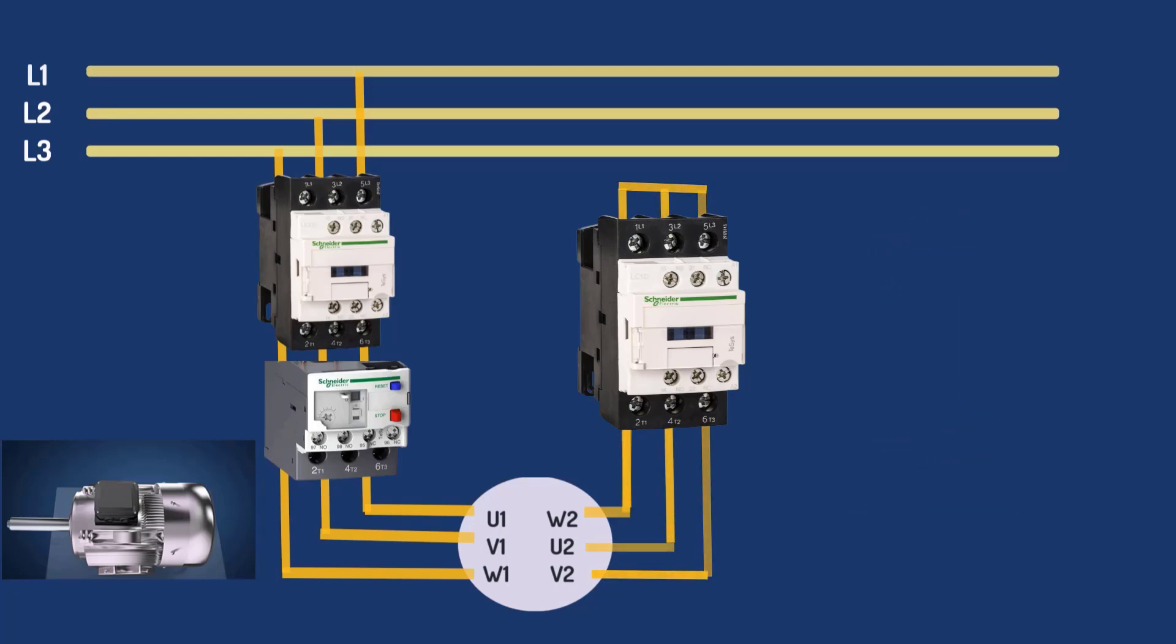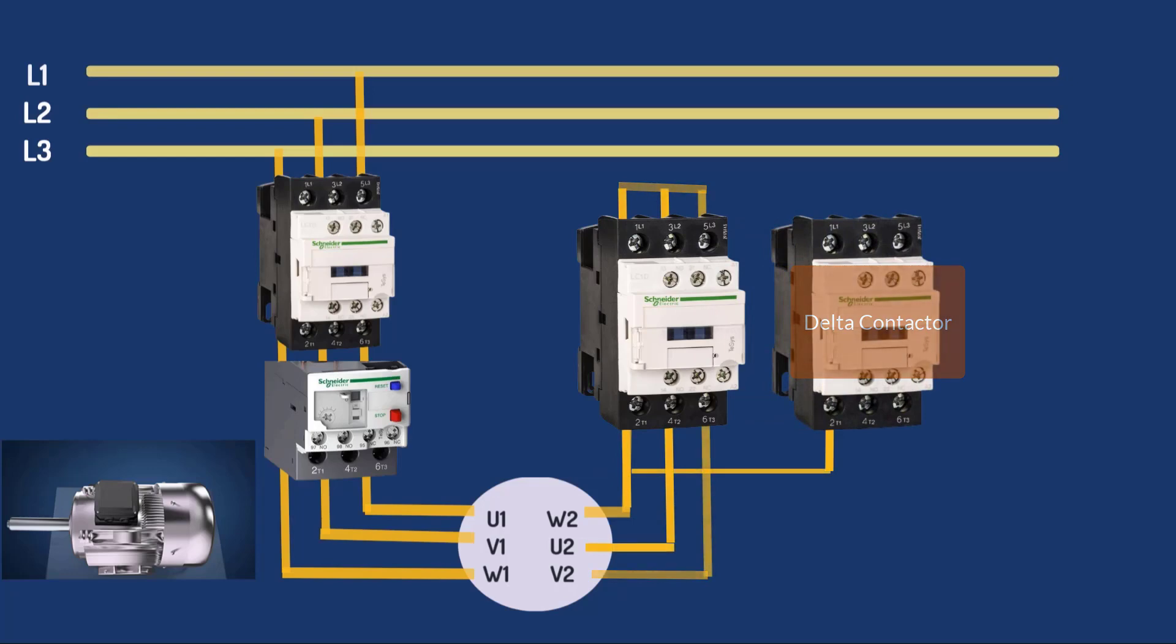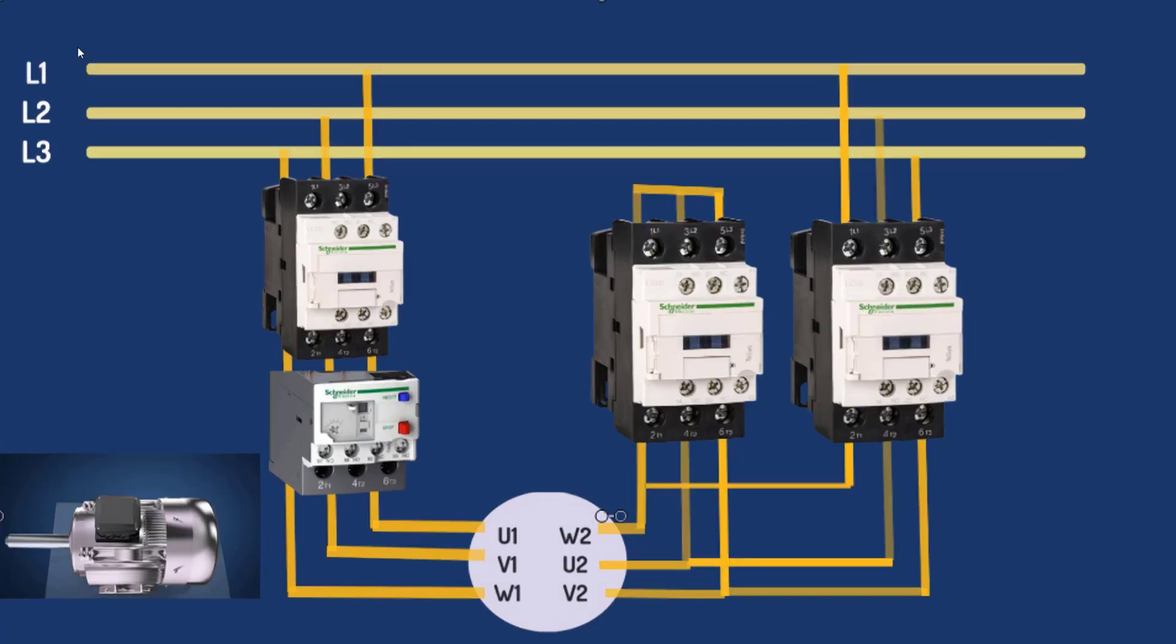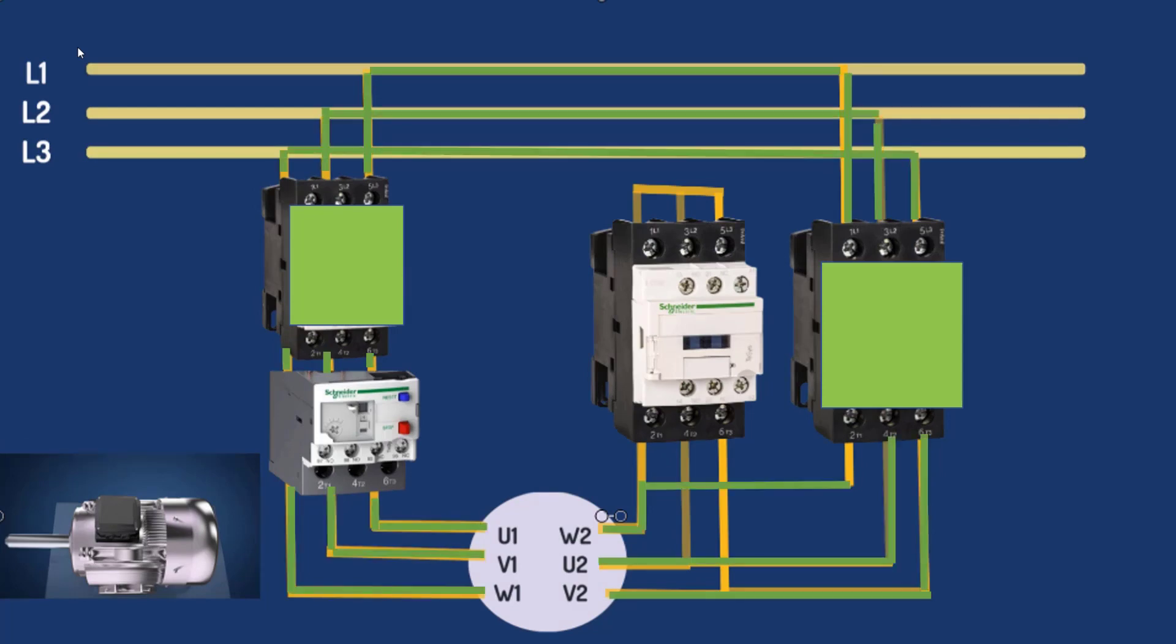Which means the delta contactor is now on. In delta motor winding connection, we will add another contactor here and connect it to W2, U2, and V2 terminals of the motor. We would wire the other end of the contactors to L1, L2, and L3 respectively. When main and delta contactors are energized, U1 will be connected to W2, V1 to U2, and W1 to V2. In this case, the motor will run in delta connection.